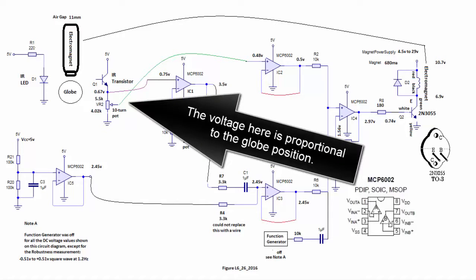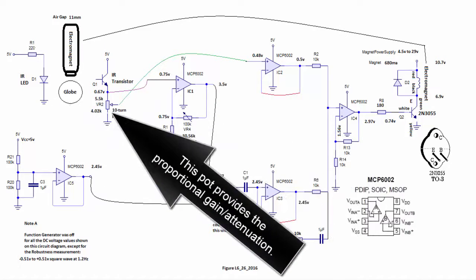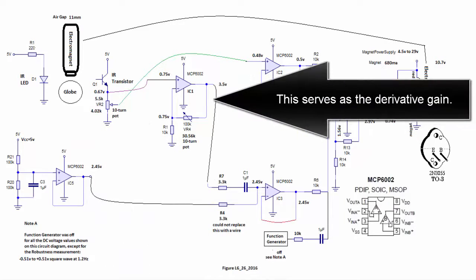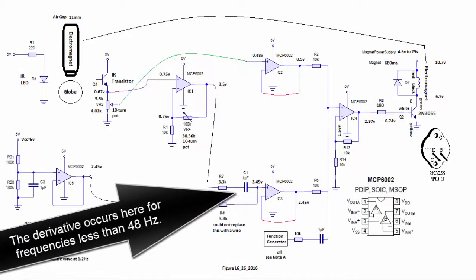The voltage here is proportional to the globe position. This pot provides the proportional gain — actually attenuation in this case. This component serves as the derivative gain, and the derivative occurs here for frequencies less than 48 Hz.